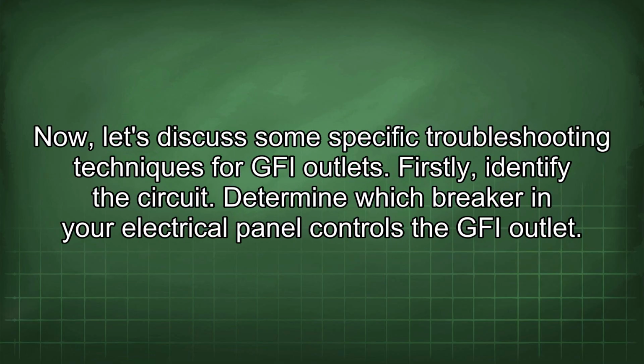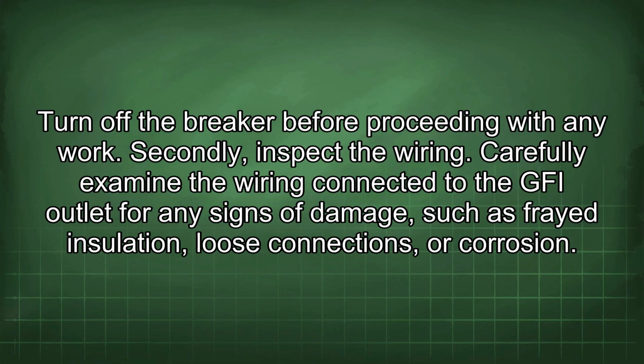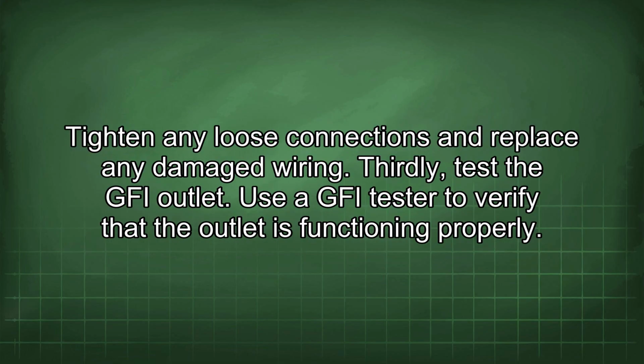Now let's discuss some specific troubleshooting techniques for GFI outlets. Firstly, identify the circuit. Determine which breaker in your electrical panel controls the GFI outlet. Turn off the breaker before proceeding with any work. Secondly, inspect the wiring. Carefully examine the wiring connected to the GFI outlet for any signs of damage, such as frayed insulation, loose connections, or corrosion. Tighten any loose connections and replace any damaged wiring.